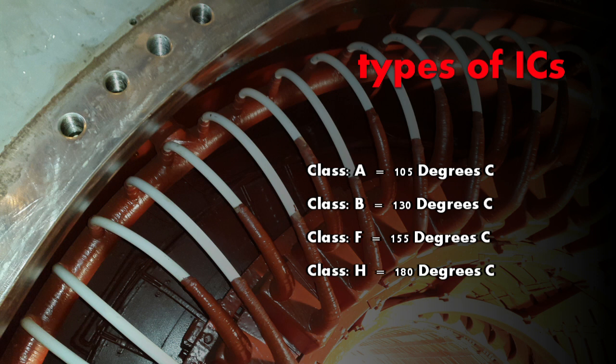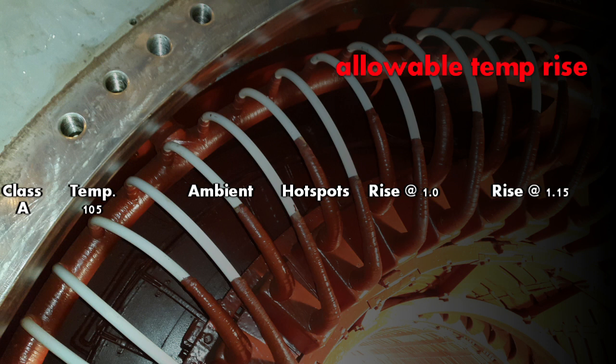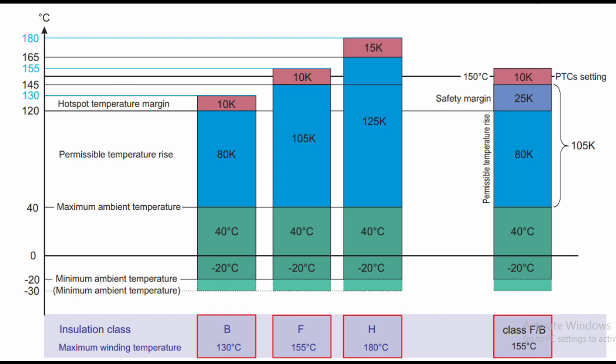Nowadays, the practice in industries is to address these classes in the form of permissible temperature rise. If we assume the ambient temperature to be 40 degrees centigrade and we take the hot spot temperature margin to be 10 degrees centigrade for B and F Class, and 15 degrees centigrade for H Class, allowable temperature rise will be 80 degrees for Class B, 105 degrees for Class F and 125 degrees for Class H. The industrial practice is to use Class F insulation with 80 degrees centigrade rise, which is allowable temperature rise of Class B insulation. It may be termed as Class FB. We have 80 degrees centigrade permissible temperature rise. What is the benefit of this? We have a 25 degrees centigrade safety margin in this. It increases the life of the motor by up to 5 times.